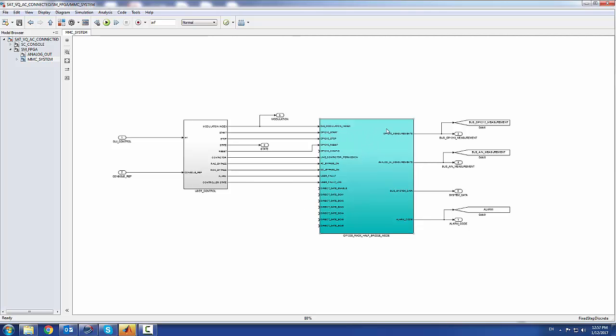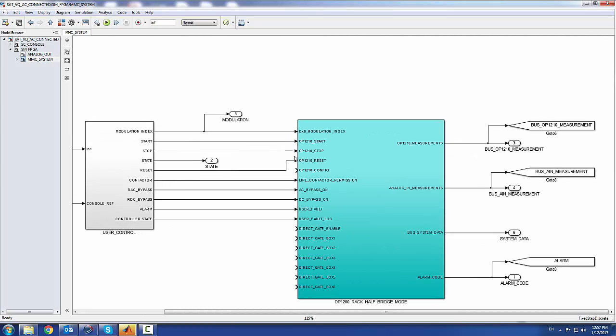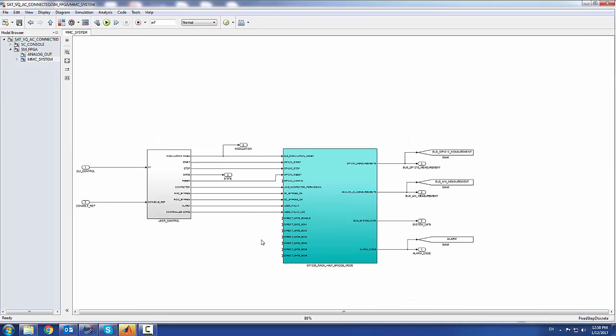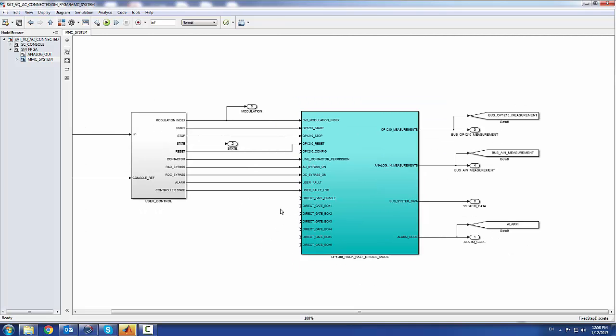You have all your digital inputs to start, stop, reset, configure and control your bypass contactors and line contactors as inputs to this block. You have two options: you can send modulation indexes directly to the FPGA on the OP4510, which comes with a demo low-level control, or you can make your low-level control inside RTLAB in the CPU system. Here's another way you can transfer your gate signals to the system.